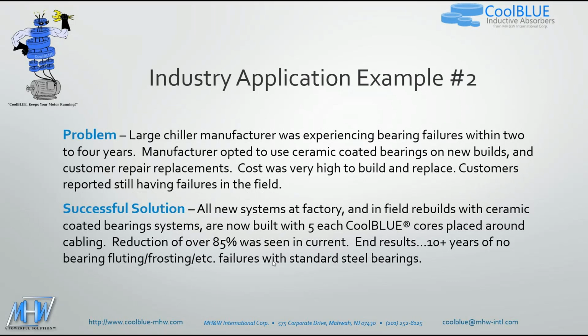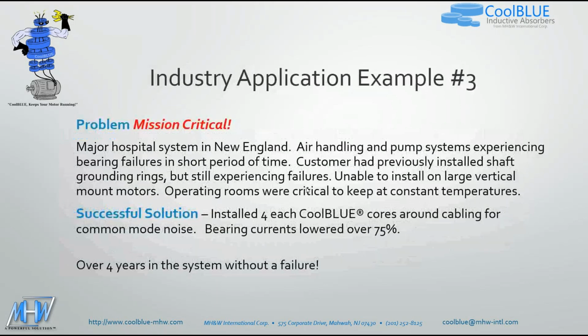The solution: basically all new systems at the factory and in the field rebuilds with ceramic coated bearing systems are now built with 5 CoolBLUE cores placed around the cabling. They had a reduction of over 85% in the high frequency current. End result was 10 plus years of no bearing fluting, frosting, etc. or failures with their standard steel bearings. So they were able to eliminate the cost of the ceramics, and they've been going 10 plus years now with no failures. And that was on a chiller.